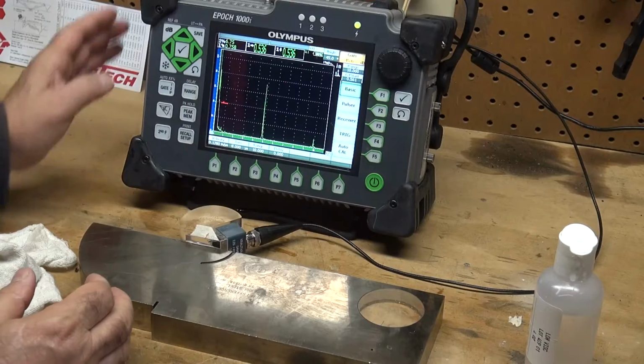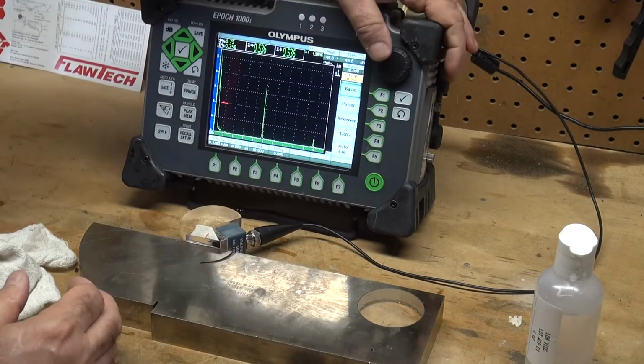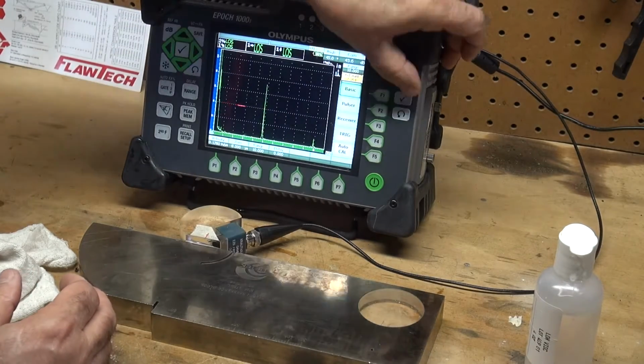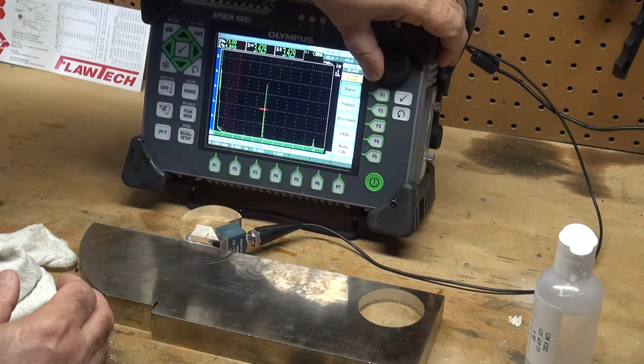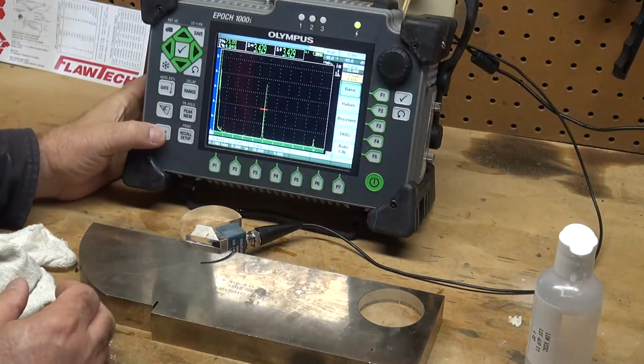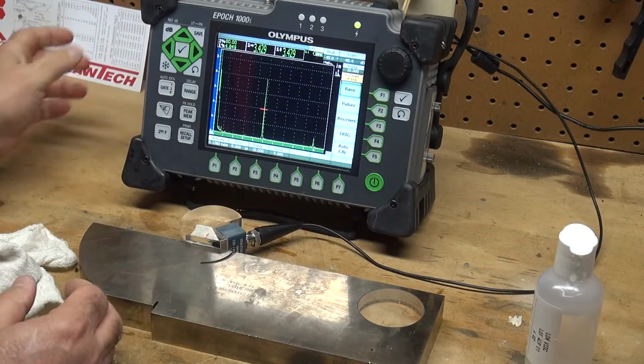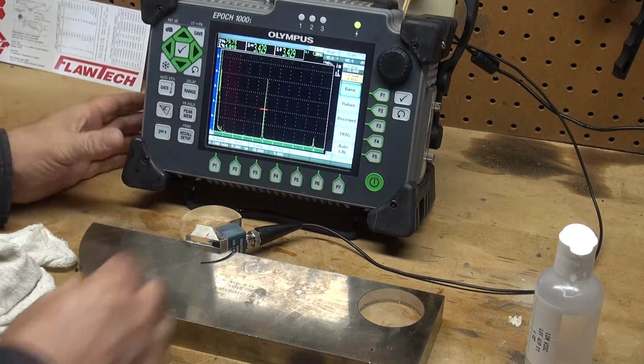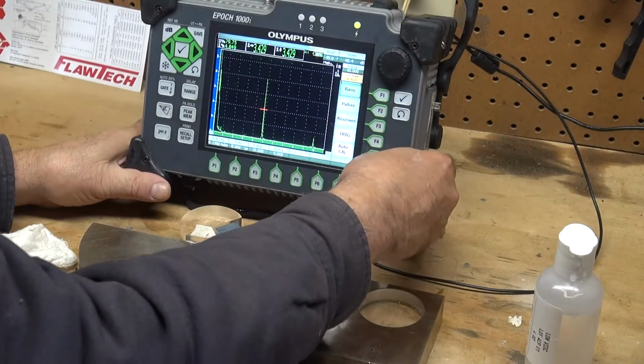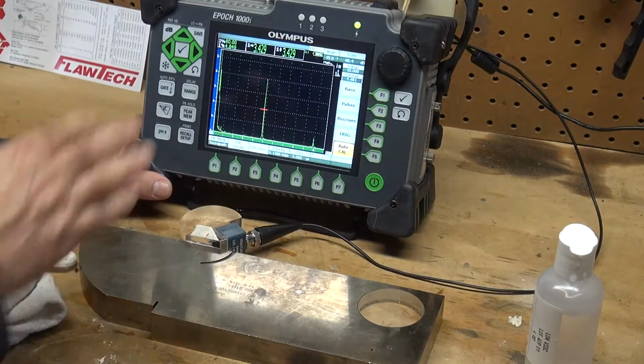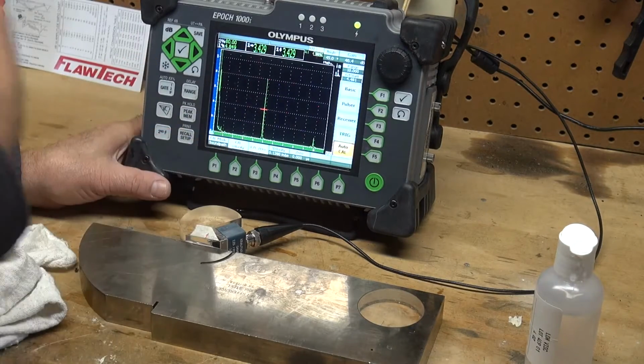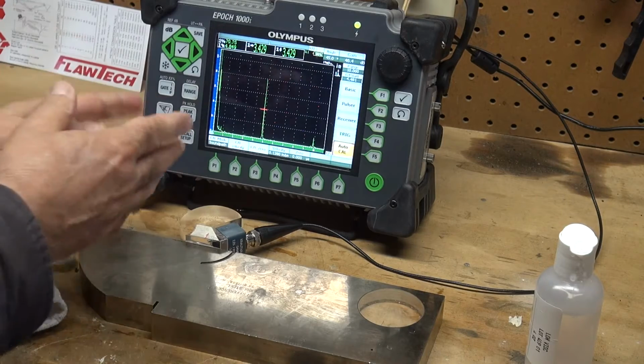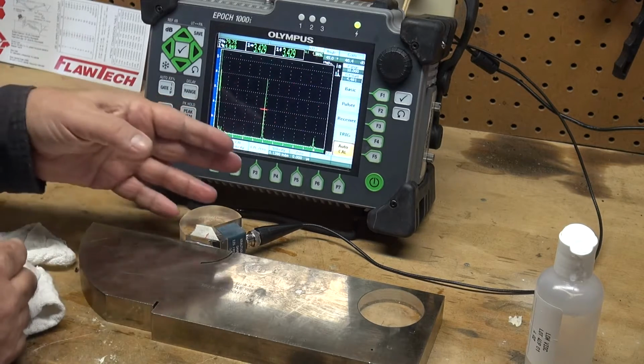So to calibrate, I want to take my gate and move my gate over to capture that 4-inch radius. I want to do second function, auto 80, take it to 80% full screen height. I want to press F5, which is my auto cal button, and cal mode is sound path, and it has cal velocity and cal 0.